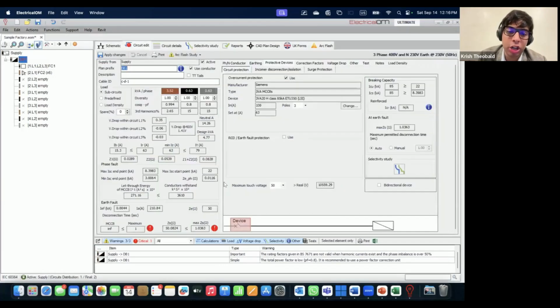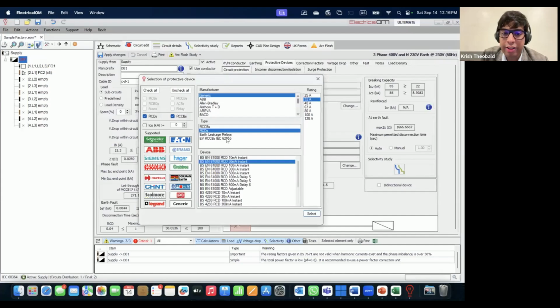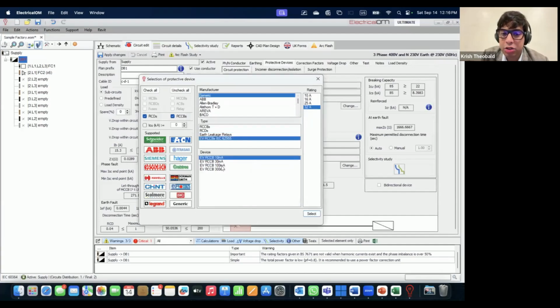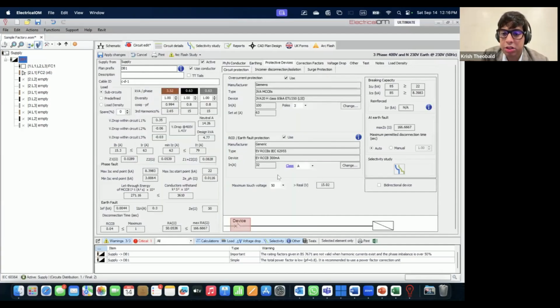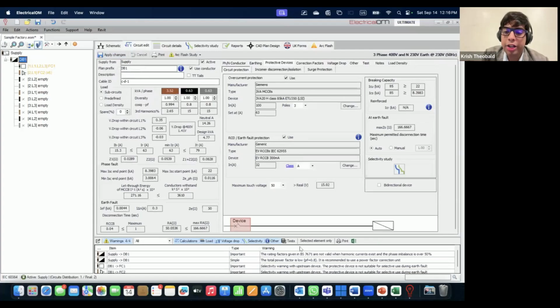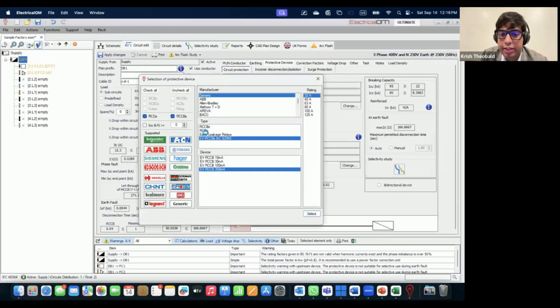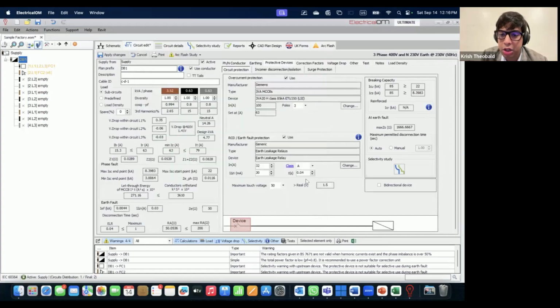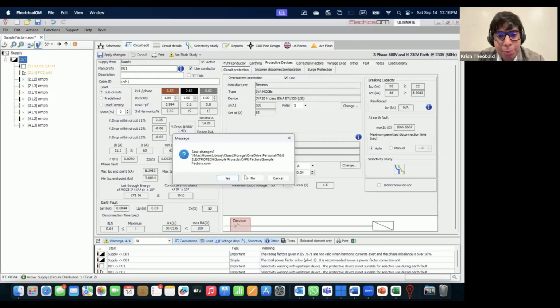But now it's giving me an issue here. There is nothing here. So now I will add an RCD here again. So here I will probably need to add a relay, say 300 milliamperes here. Now it is giving me a warning because both are this thing. So if I go here, I say earth leakage relay adjustable and whatever. So basically you get the point. I can add an earth electrode, but how many earth pits are required? That is a ridiculous question because that is not a matter for low voltage installations in any case.